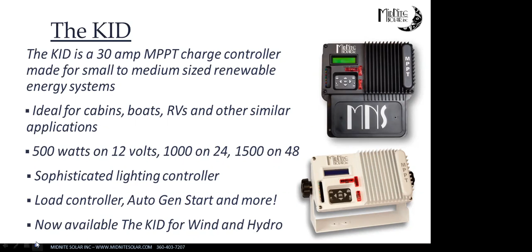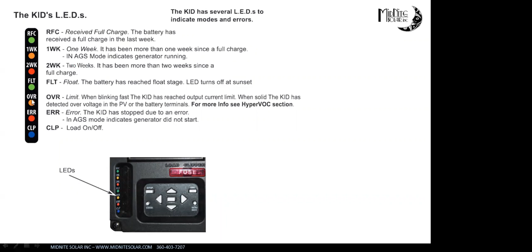One of the things I like about the KID is the little LEDs. The top three are probably the most valuable for me. The green light comes on if it's gone to float. If it goes 7 days without going to float, the orange light comes on, letting you know at a glance that you haven't had a full charge. The blue light comes on if the load circuit's active, and the OVR light comes on if you're over the current limit of the KID.